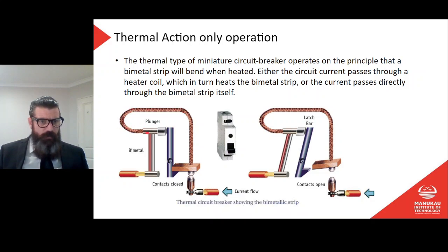And here we have a little diagram of how that works. Current flow coming through here, through here, through here, down here, and that will be our output there. And we have our contacts closed. When things start to move, then the plunger pushes the latching bar. The latching bar is holding, see here, the contacts closed. As soon as that latching bar moves, then the contact is free to open, and therefore the circuit is open.